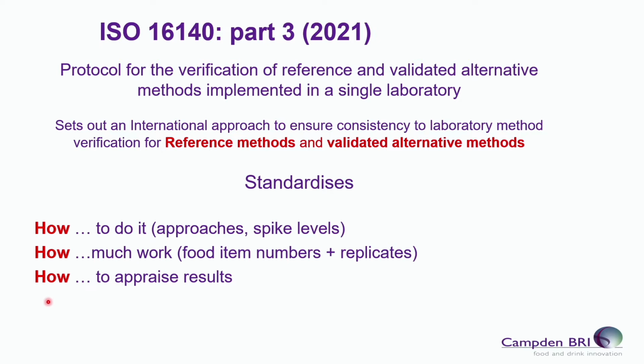And basically what this standard does is it sets out an international approach to ensure consistency to laboratory method verification for reference methods and validated alternative methods. This is a key part actually, because where we've been talking about method validation, the only methods you need to validate are proprietary methods. ISO reference methods don't need to be validated, they're taken to be valid. Methods that have to be validated are proprietary methods.